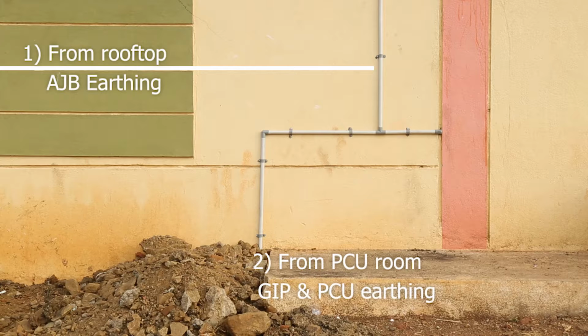One set of wire, positive and negative, goes inside the house to connect the power conditioning unit. One wire, green color 10 square millimeter, through the pipe goes to the earth for earthing the array junction box.